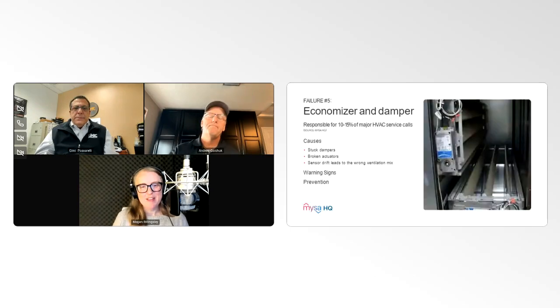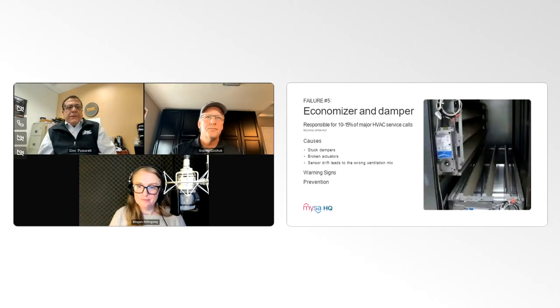Excellent. Thank you so much. So let's move on to the fifth and final cause of HVAC failures we'll discuss today, the economizer, the unsung hero of efficiency. Gino, what are signs of an economizer failure? Okay, economizer failures. This is a passion of mine. This is probably the number one issue that I find when we service rooftops. For whatever reason, we find them disconnected, inoperable, not sensing the right outdoor air temperature or indoor air temperature, humidity, and dry bulb temps.